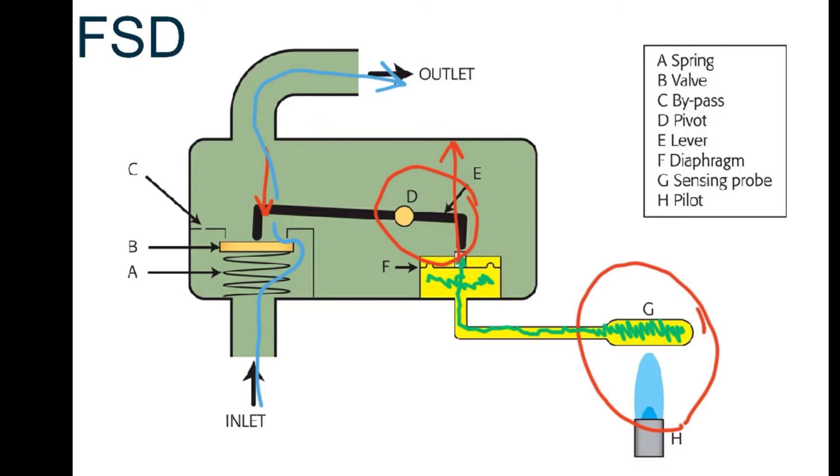If the pilot is cold and this valve is closed, you can still get a small amount of gas going through the bypass. This small amount of gas which is going through the bypass allows the burner to light at the low flame when this main valve is closed.